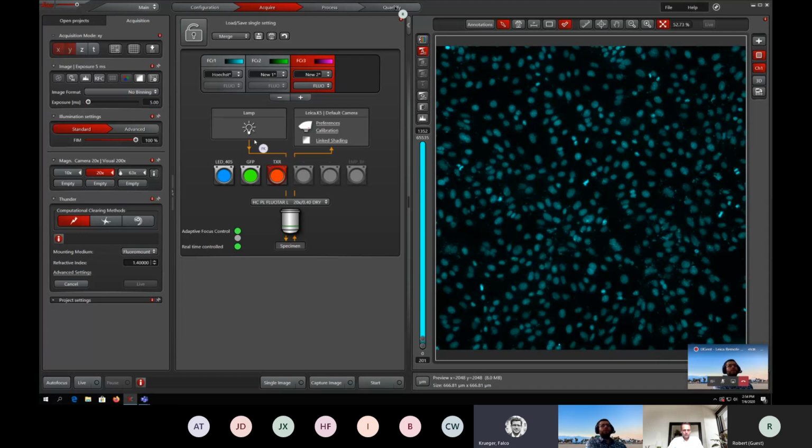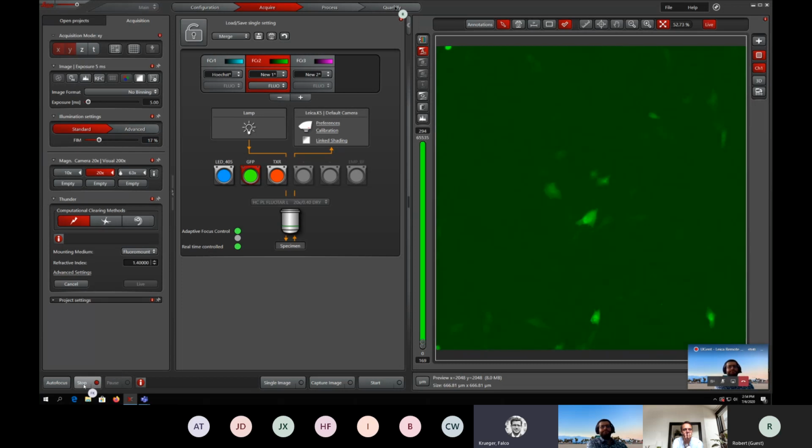Good. And now we need to set up the options or the properties of the individual channels. So for channel DAPI, we have exposure 5 milliseconds and the input intensity is 30%. Image is quite nice. Maybe we go here to 10, just to have even more light, even better signal to background. Now we are above 10:1. Second channel, 5 milliseconds, 17% input light.